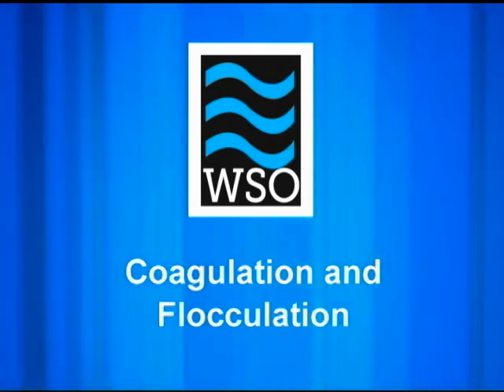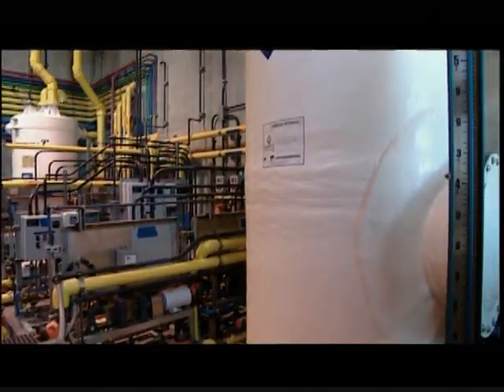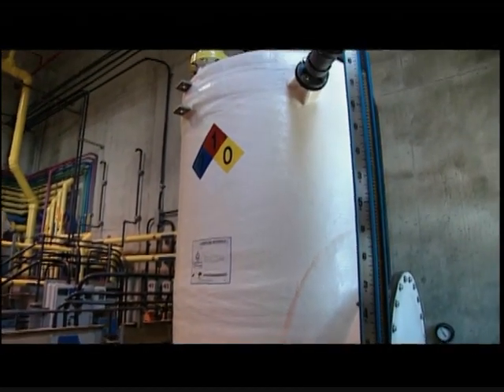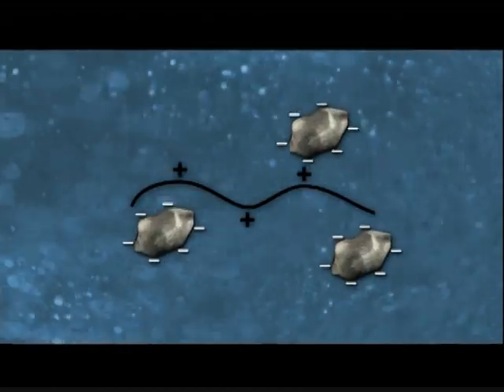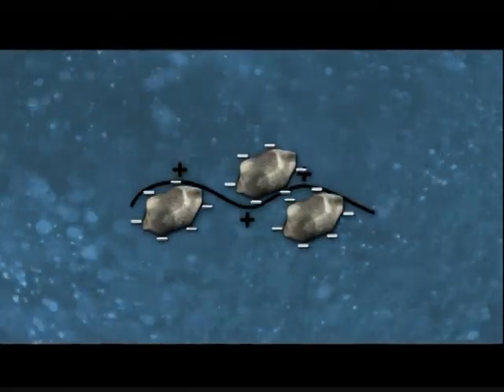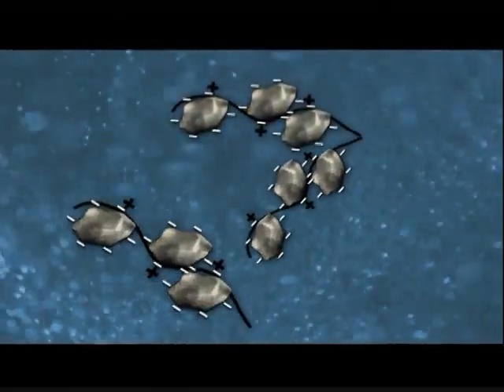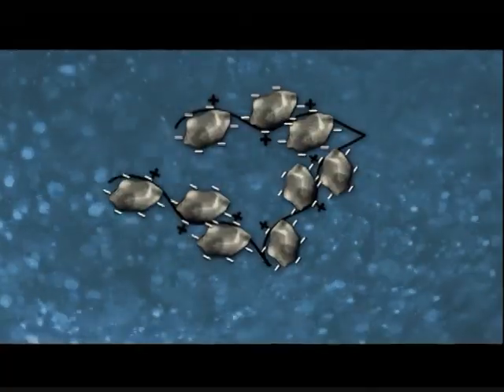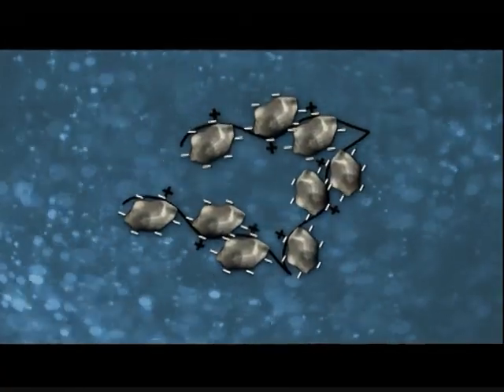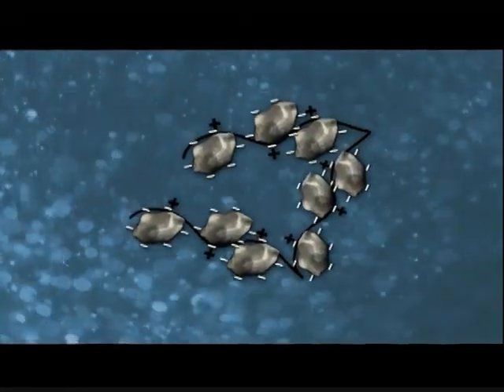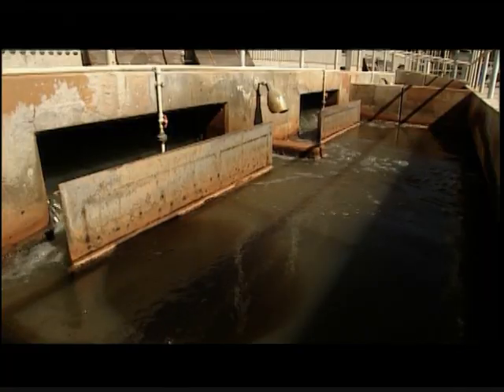Coagulation is the addition of chemicals to destabilize the electrostatic forces of non-settlable solids. Coagulant chemicals typically have a positive charge, which binds to the negatively charged particles in water, neutralizing them and allowing them to come together to form small clumps of particles called microfloc.